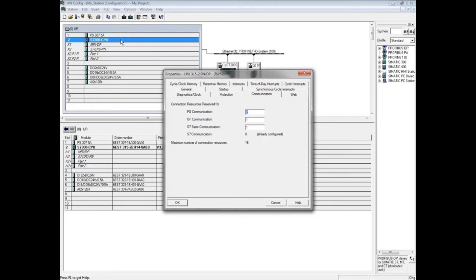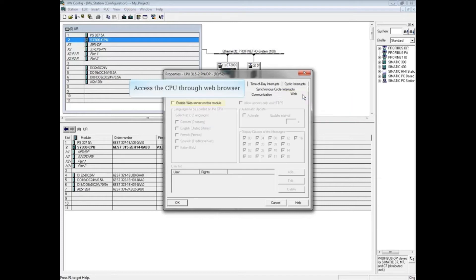The web tab only shows if you are using a PROFINET CPU. Click on the web tab. Select Enable Web Server in order to access the CPU from a web browser.